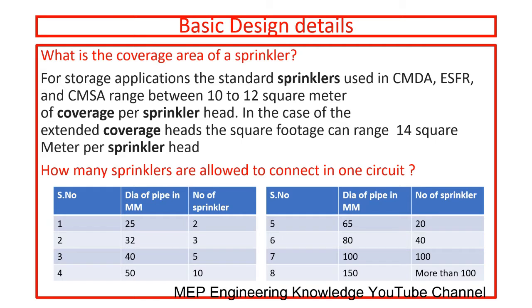Let us understand the coverage area of a sprinkler. Each sprinkler will cover approximately 10 to 12 square meters. In case of extended coverage, the area can range up to 14 square meters per sprinkler head. We can learn more detail about the number of sprinklers that can be tapped in each pipe. This tabular column will give a clear picture for your quick understanding.